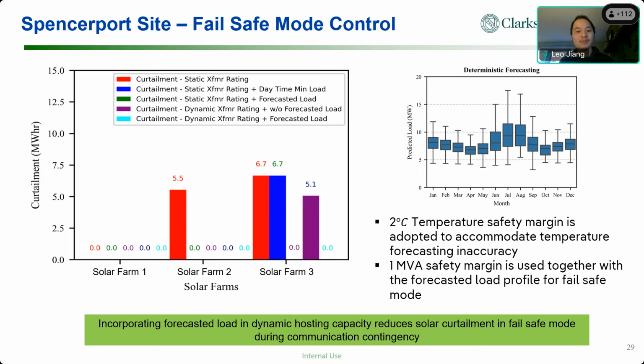So that makes our analysis very conservative, which, as I said, from the utility implementation perspective, we would like to be. But here, the only difference is that we want to be reasonably conservative. So basically, incorporating the forecasted load in the dynamic hosting capacity reduces solar curtailment in the fail-safe mode during a loss of communication event.